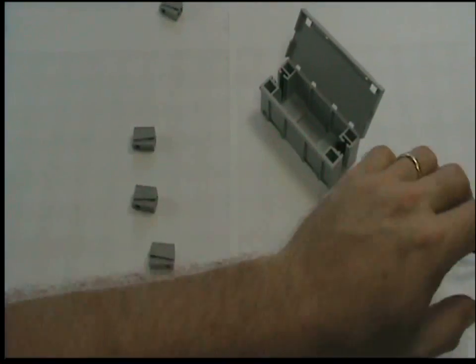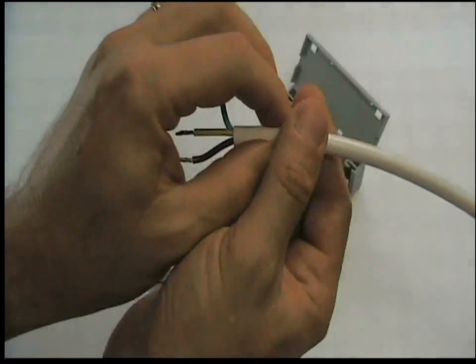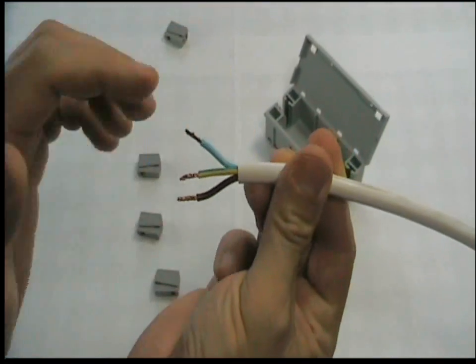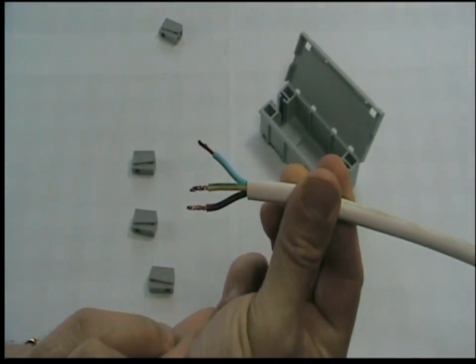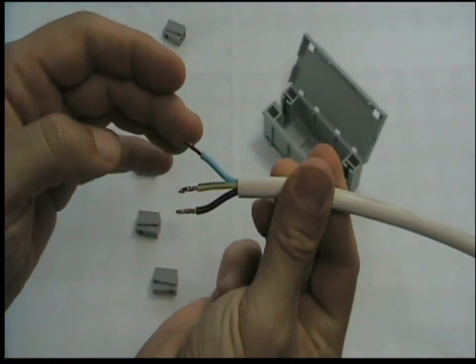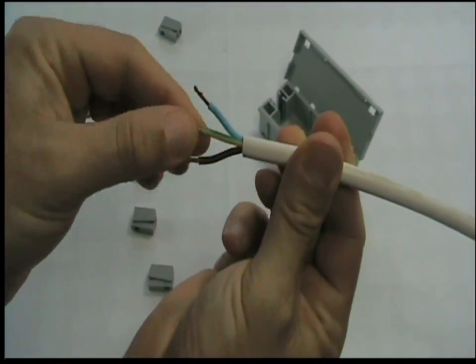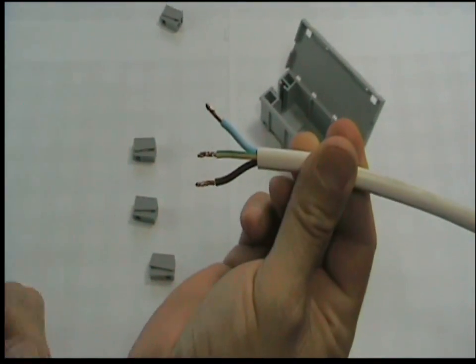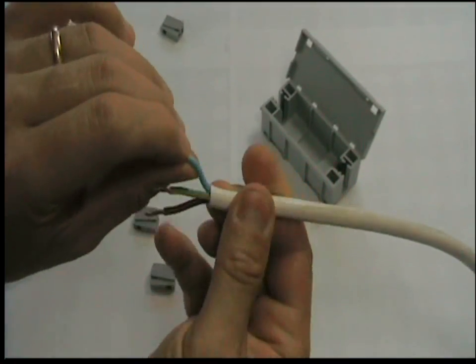To prepare our cables we first need to strip off 35mm of the outer sheath. Then we strip off 10mm of the cable insulation. Once this is done we are ready to connect our WAGO terminals.